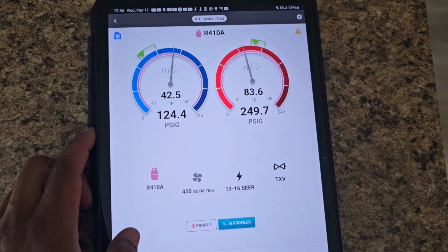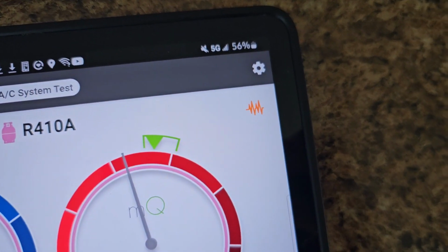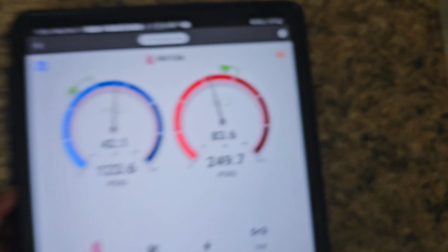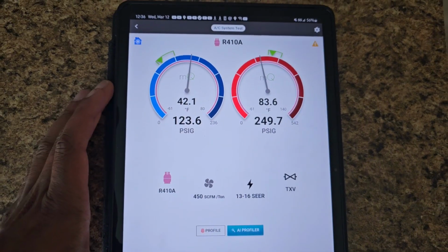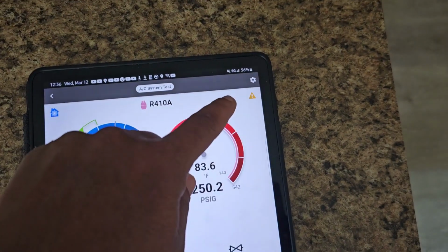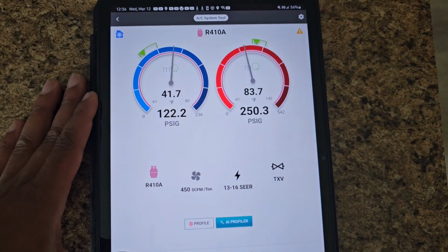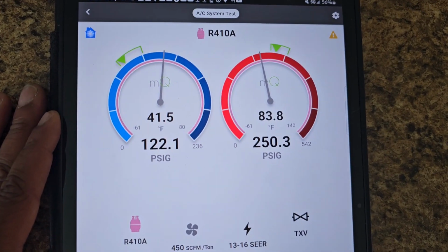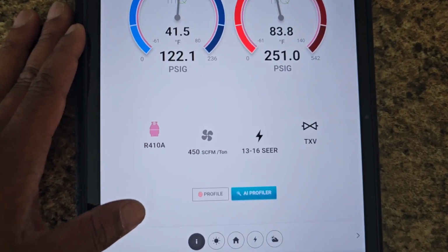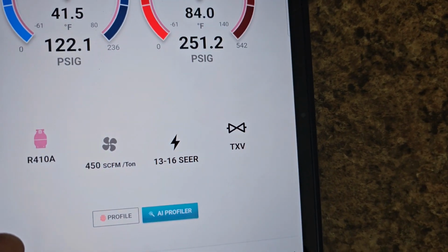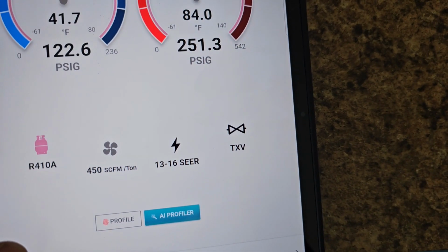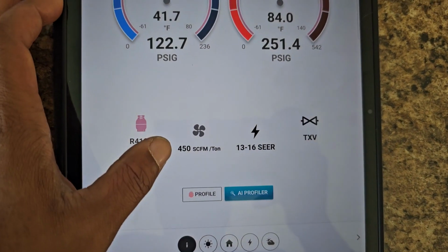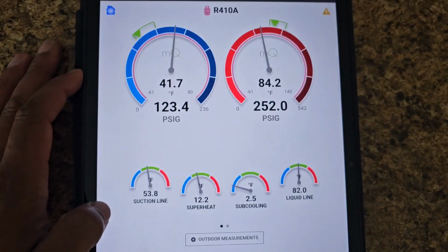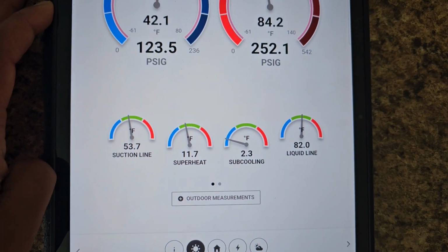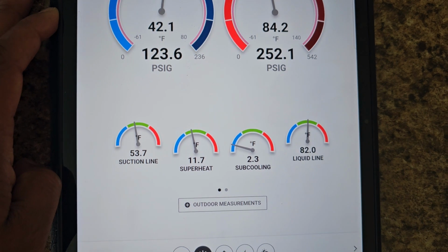Weird. All right, y'all. The system has been running long enough for the fault indicator to go away, so it can give a fault code, or an idea of what might be wrong with the system. But these are the pressures we're working with right now. Inputted that we're working with the TXV, with the bulb on the outside of the suction, on the outside of the coil, and 450 CFM per ton for the area. These are the subcooling and superheat measurements right now.